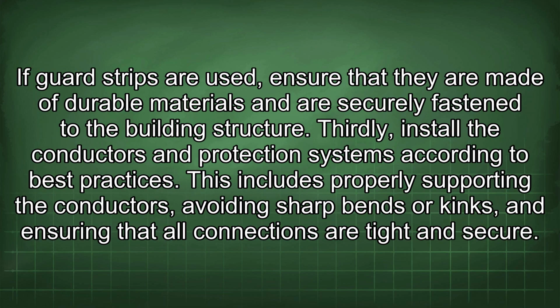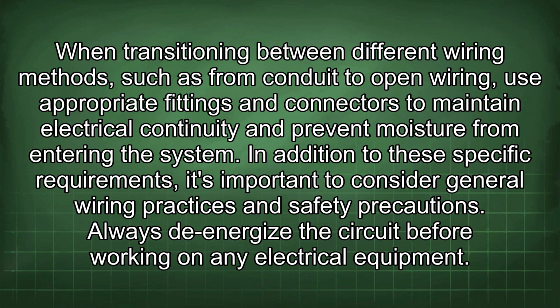If guard strips are used, ensure that they are made of durable materials and are securely fastened to the building structure. Thirdly, install the conductors and protection systems according to best practices. This includes properly supporting the conductors, avoiding sharp bends or kinks, and ensuring that all connections are tight and secure. When transitioning between different wiring methods, such as from conduit to open wiring, use appropriate fittings and connectors to maintain electrical continuity and prevent moisture from entering the system. In addition to these specific requirements, it's important to consider general wiring practices and safety precautions.